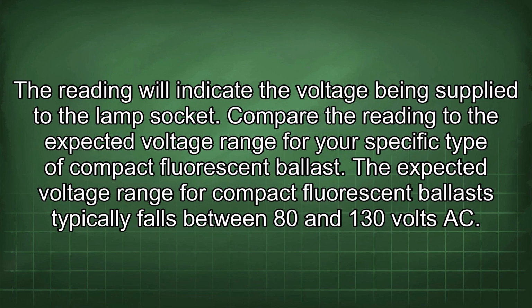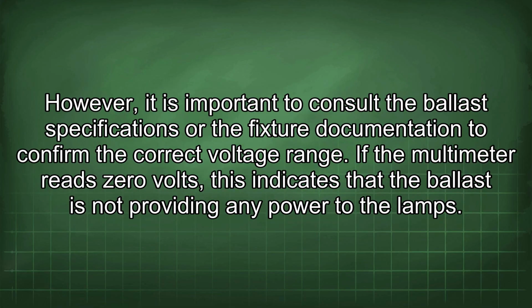Compare the reading to the expected voltage range for your specific type of compact fluorescent ballast. The expected voltage range for compact fluorescent ballast typically falls between 80 and 130 volts AC. However, it is important to consult the ballast specifications or the fixture documentation to confirm the correct voltage range.